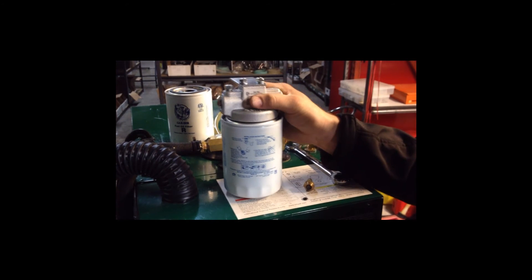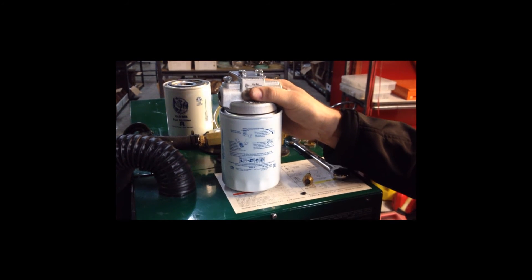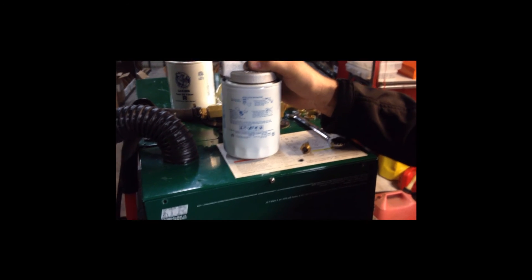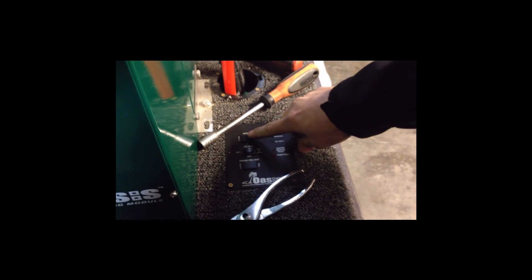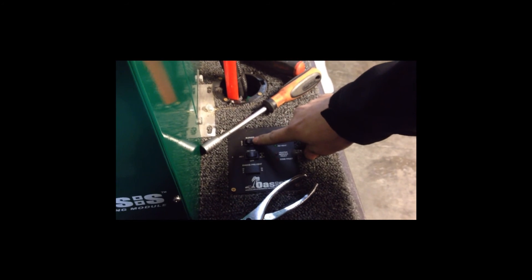And now we have completed a 5 year service kit on our Oasis CH50. Next thing we want to do, turn the power back on and turn the burn switch back on. We want to make sure that igniter is going in there and the heater is going to fire off. Nice bright flame, that's what we want to see.